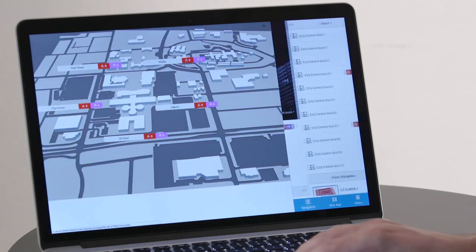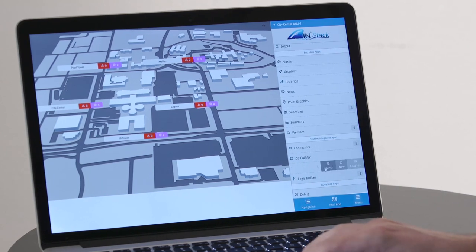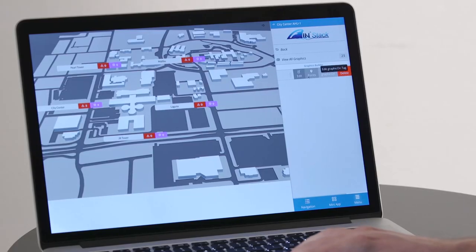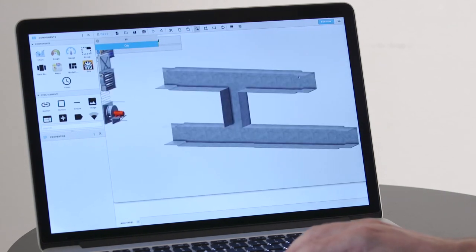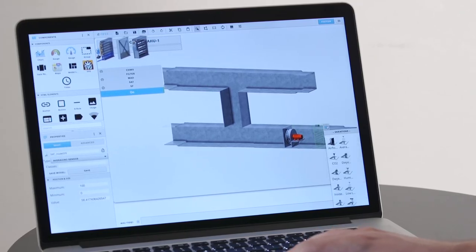Now let's take a look at engineering the job — remember we changed the workflow 180 degrees. Everything you saw previously with magic bubbles and things running on the phone can now work automatically, and this is how you do it. Navigate to where you want to go — let's go to an air handler, go in the smart menu, go to the graphics builder, and hit new graphic. A wizard opens up to create our graphic. I'm going to name the air handler and select the points that I want. The wizard automatically, based on the points I clicked on, tries to guess which objects you wanted to use. Let's go ahead and move those graphic objects around.